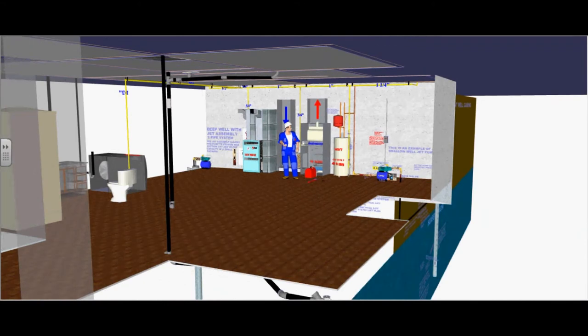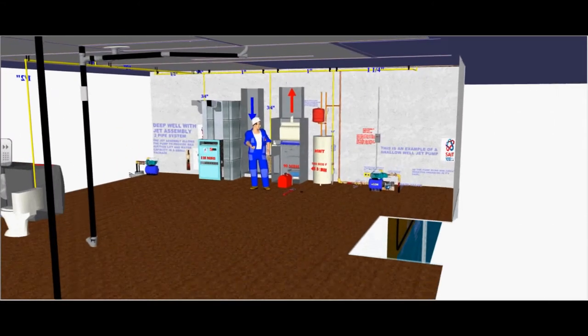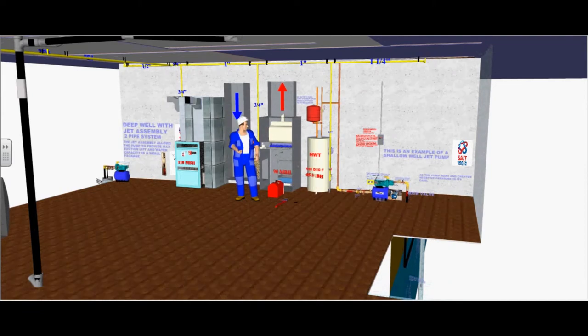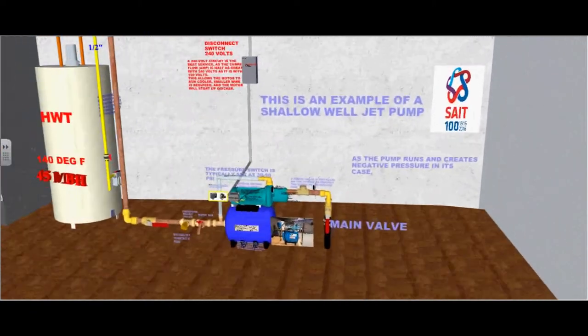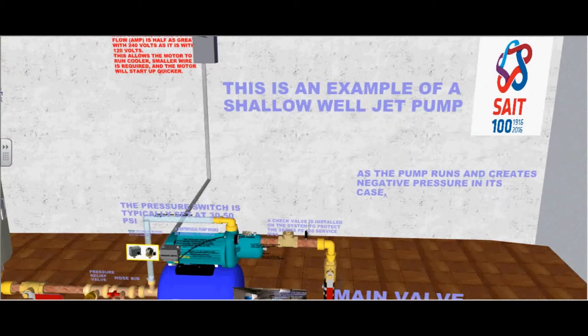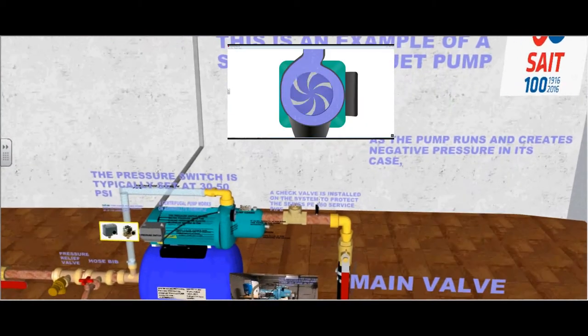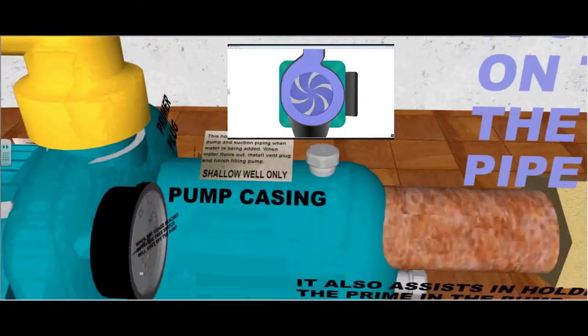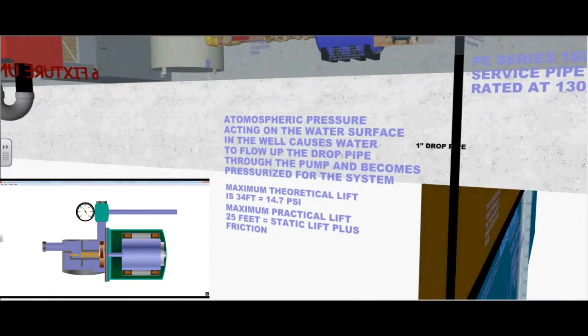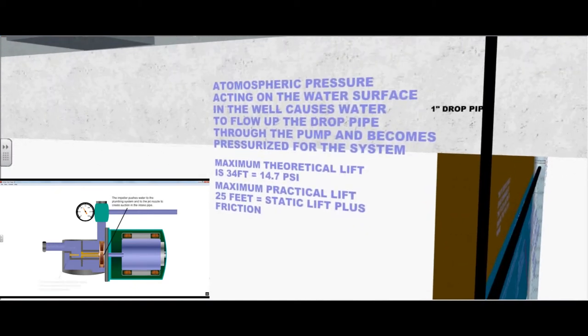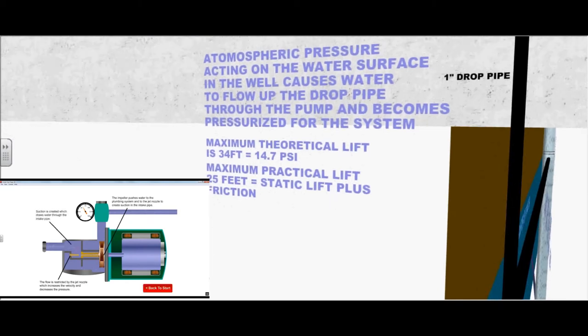Let's follow this polyethylene service pipe into the mechanical room. Here is an example of a shallow well jet pump. As the pump runs and creates negative pressure in its pump casing, this is the volute casing. Atmospheric pressure acting on the water surface in the well causes water to flow up the drop pipe through the pump and becomes pressurized for the system.